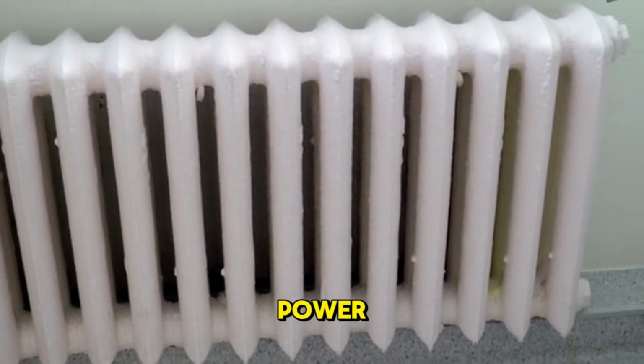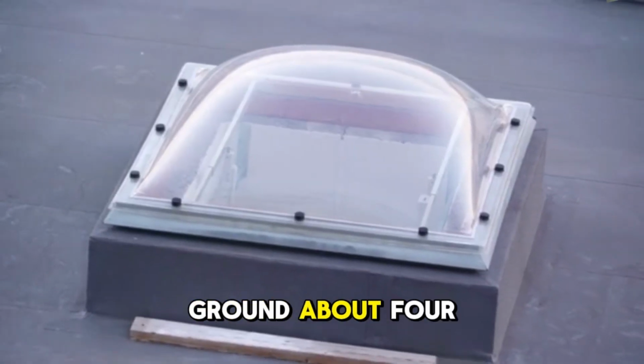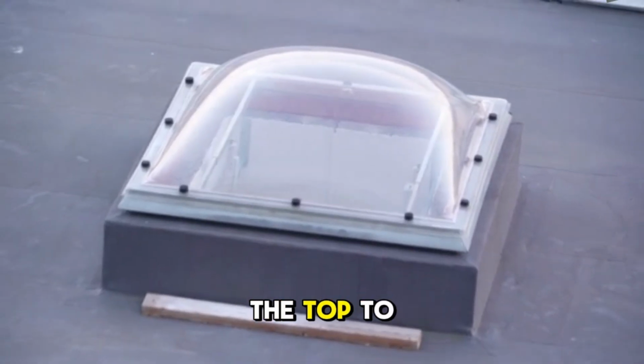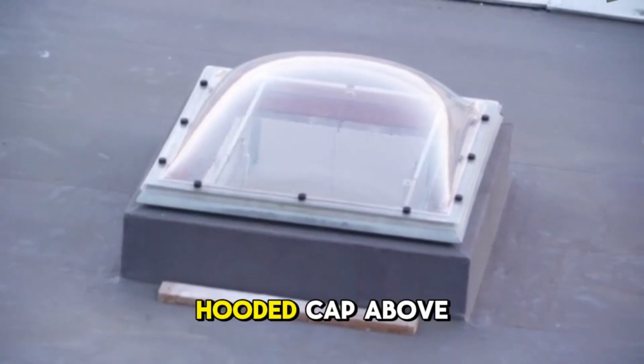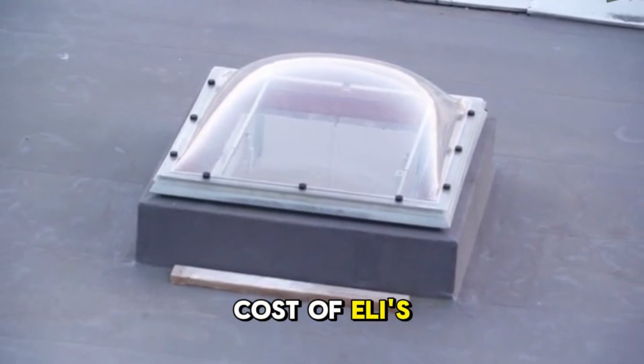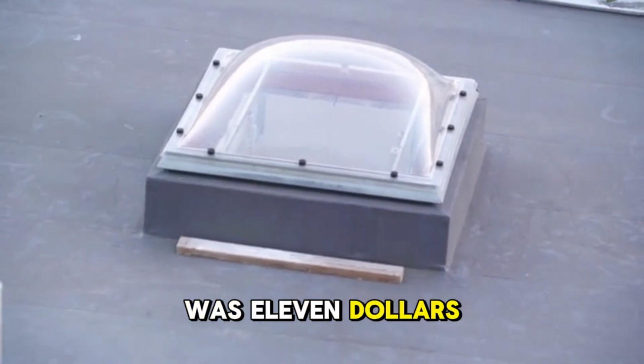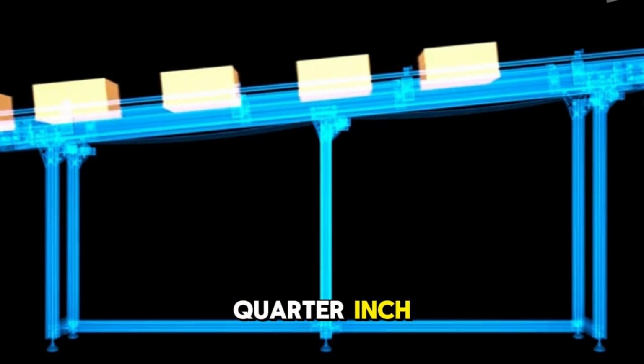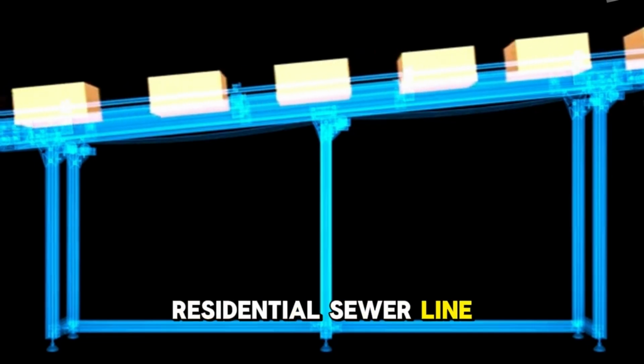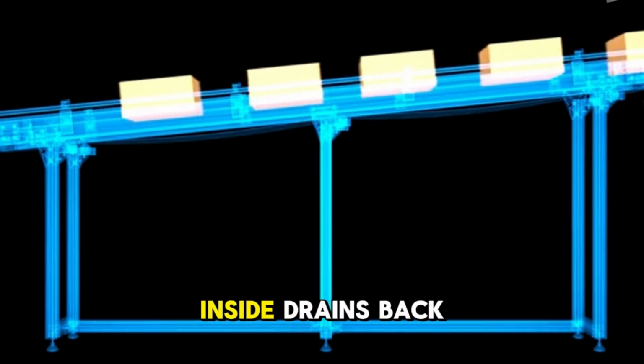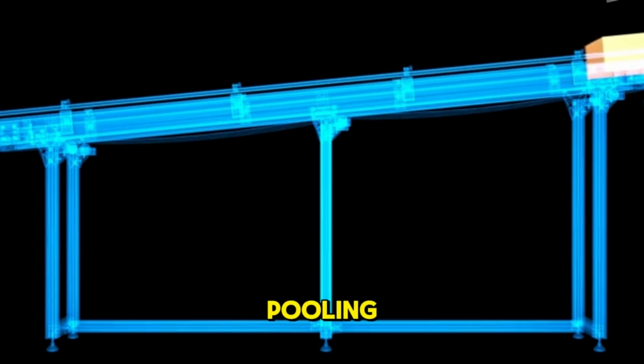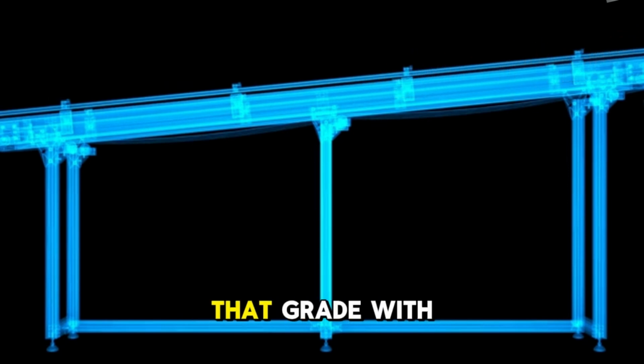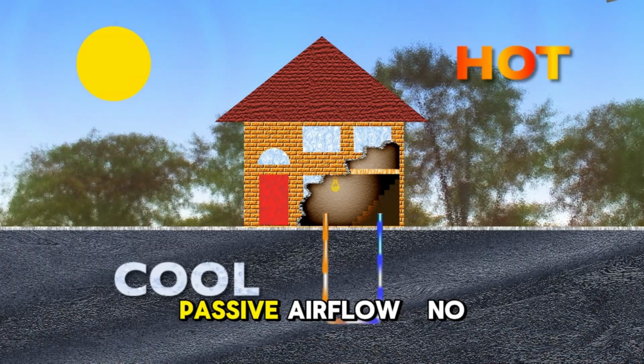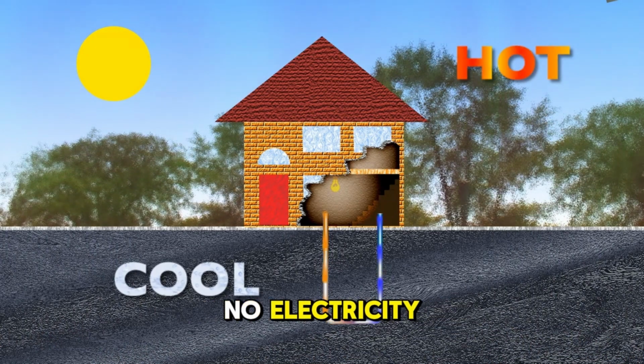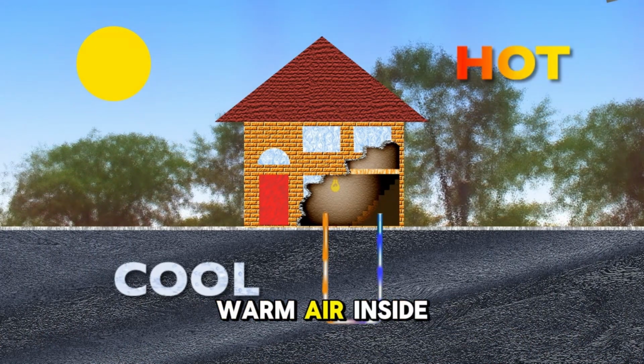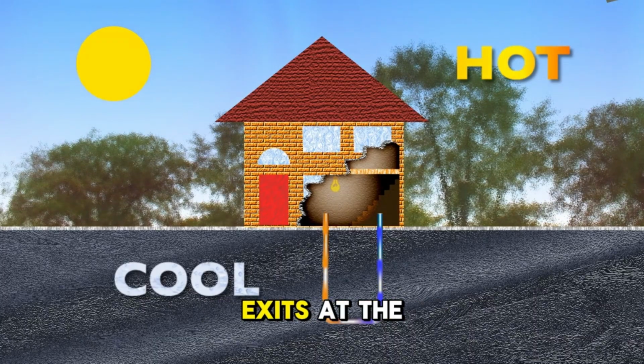The intake riser comes up vertically out of the ground about 4 feet, with a stainless mesh screen at the top to block insects and rodents, and a simple hooded cap above that. Total cost of Eli's screen in 2019 was $11. The pipe runs with a slope of 1/4 inch per foot, the same grade as a residential sewer line. So any condensation that forms inside drains back out the intake end, rather than pooling toward the house. Any homeowner can hit that grade with a string line at a basic level. Passive airflow, no fan, no electricity, works on natural convection. Warm air inside the house rises through the upper floors and exits at the top.